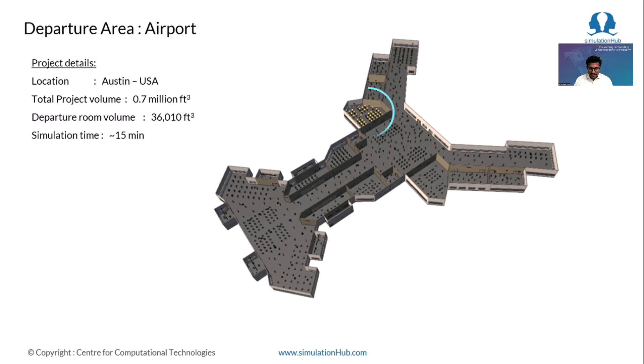AHC not only gives us the contour information, it also gives us the comfort information of the occupants present in the space in the form of emojis. For example, on the right top figure, you can see that most of the mannequins are feeling comfortable, but a single mannequin in the middle is feeling slightly chill, mostly due to the draft caused by the diffusers. At the same time, occupants located close to the walls and windows are feeling slightly warm, usually because of solar radiation entering through the glass windows.